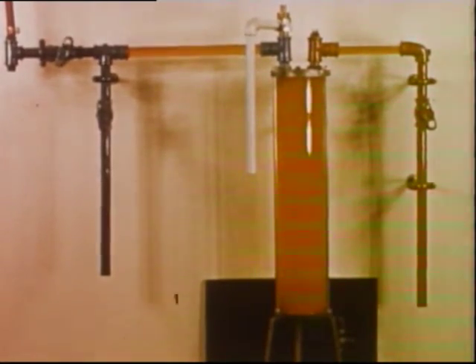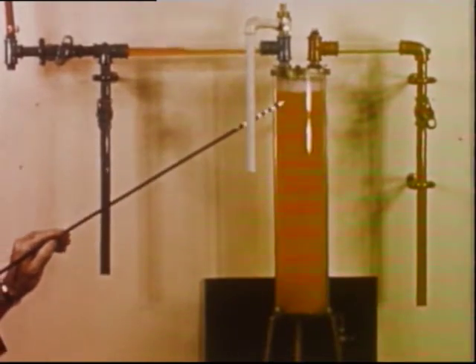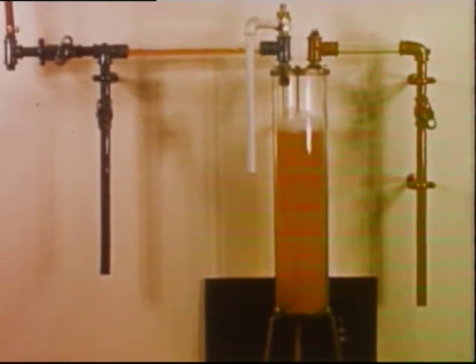In this glass tank, we will illustrate another serious hazard of overheated water, which is common to open main systems. When the superheated water starts to boil, steam forms and displaces the water, forcing it back into the cold water supply line. As the volume of steam increases, it overcomes the water main pressure and pushes this boiling water further and further back. Should a cold water outlet be opened, this steaming water can cause personal injury and also water closet breakage from sudden high temperature. This is also what causes burned out meters.